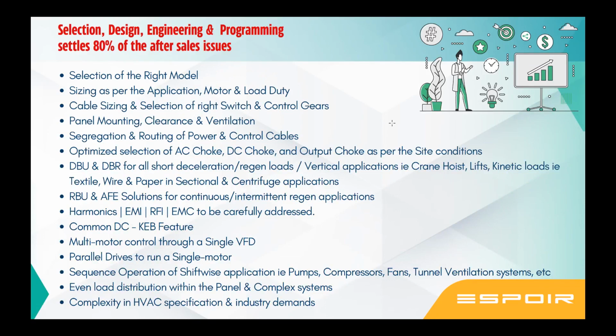Now comes cable sizing and selection. You have a proper VFD selection, but what if you have not selected the cable properly? You need to size the cable accordingly. Large motors generally have 6 cables running because you use a star-delta starter. Now, using a VFD, you need to have only 3 cables running. But what size of cable do you need to work on a star or a delta? You need a different design, so you need to select based on the application. In certain applications, people still use star mode where the torque is not important, but the speed is. In certain cases where the torque is important, you need to switch to a delta mode of winding. So you need to go through the nameplate as per the manufacturer and get these facts checked. If you have a doubt, please don't hesitate to ask the expert.